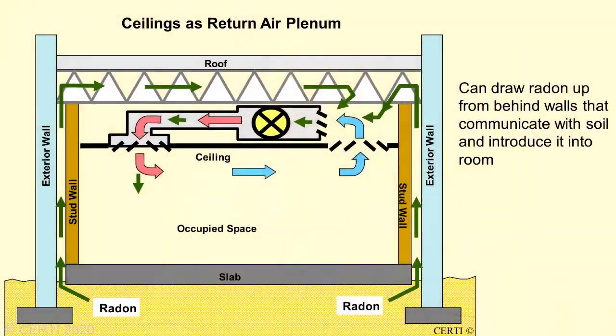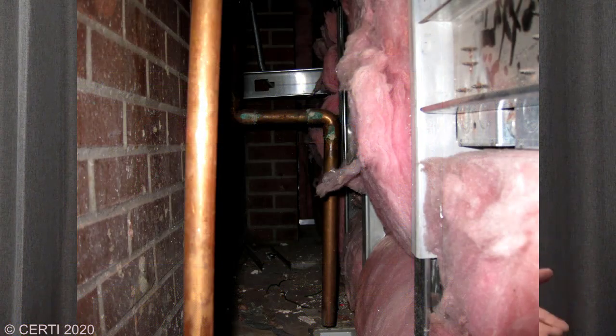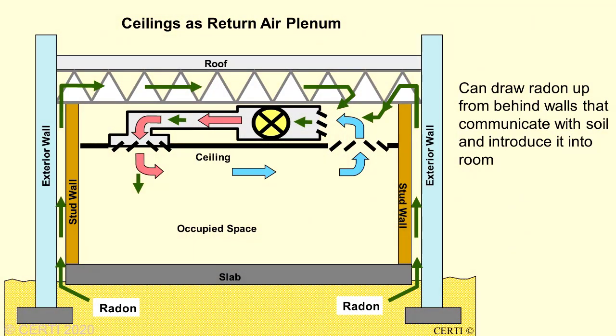Importation of radon via an air handler can also occur when the ceiling is used as the return air plenum. This is often done to reduce the cost of installing ductwork to separately run air to the forced air unit. This practice causes the entire ceiling area to be under significant negative pressure. If there are pathways to the soil, such as behind stud walls or demising walls, this can draw radon from the soil and introduce it in the air handler, where it is then distributed throughout the entire building.